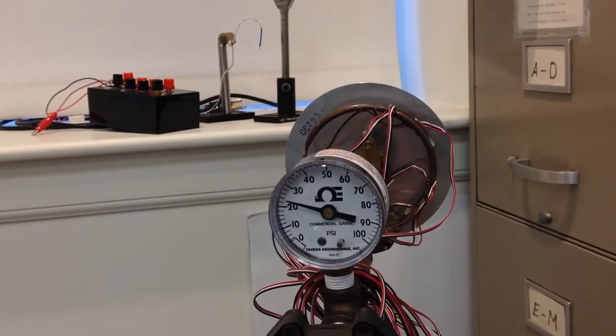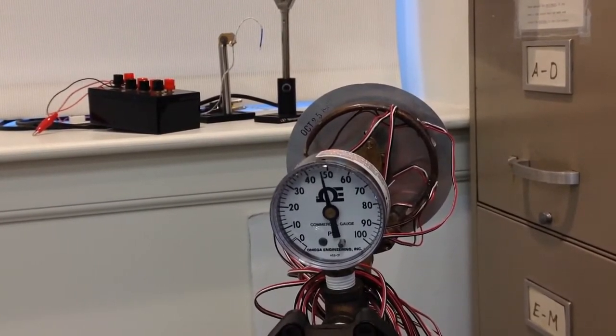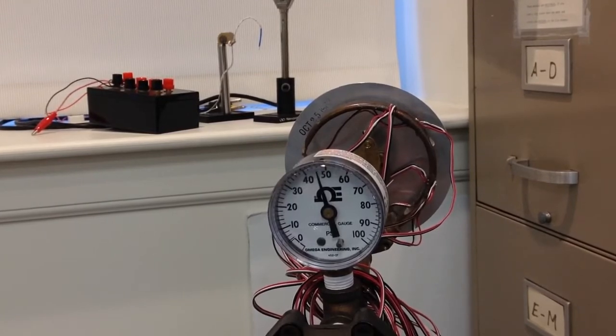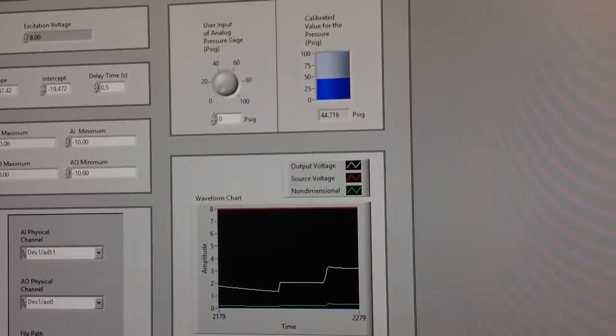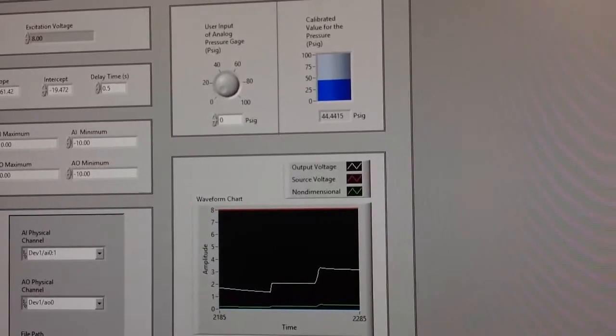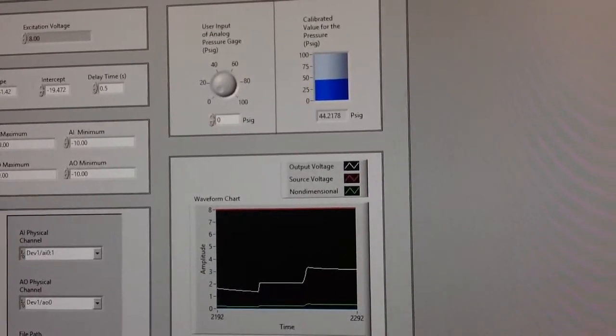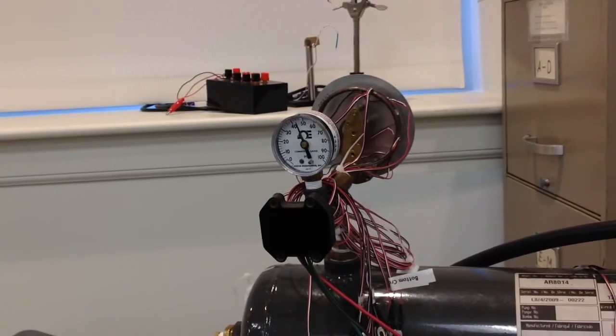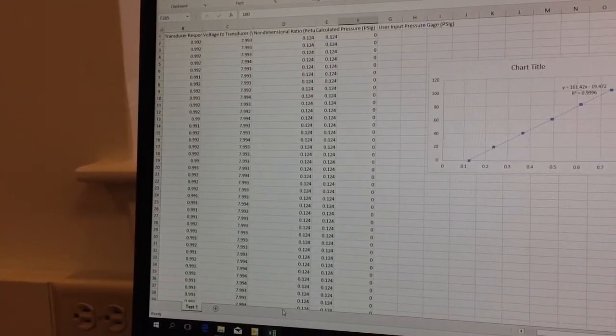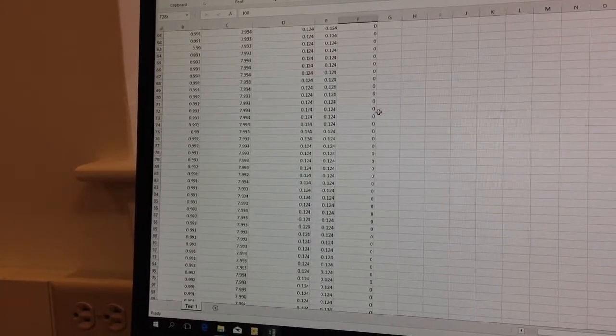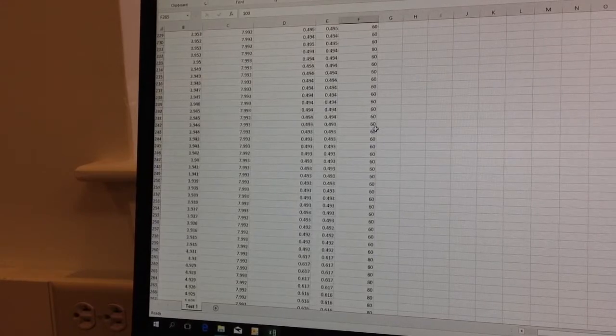And let's increase the pressure to, so right now it's around 45. So with the calibrated pressure sensor I have 45 psi, okay? So what you will do tomorrow is the calibration and verification of the calibration like I did now, okay? So for calibration you will need to obtain the data like I had here for 0 psi, for 20 psi, for 40, 60, 80 and 100, okay? So this is the minimum what you have to do, okay?